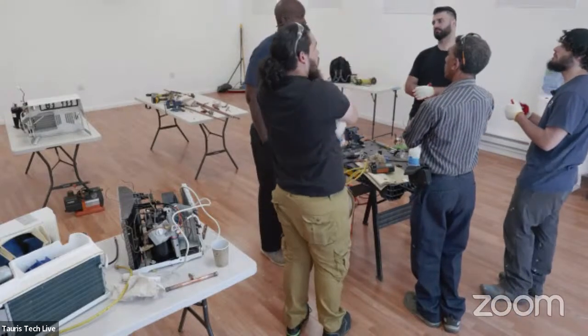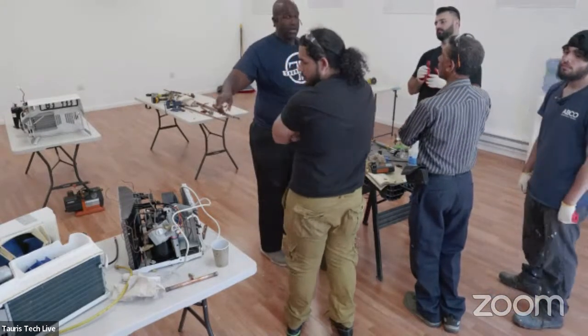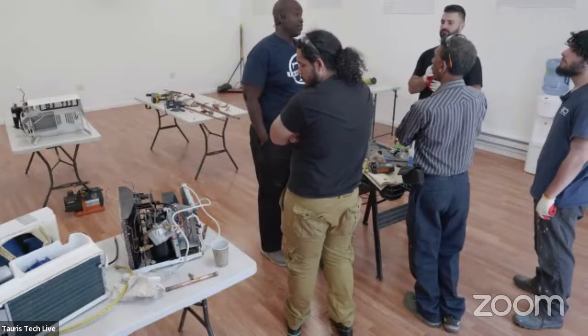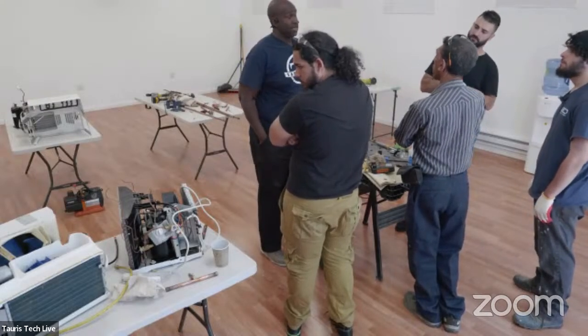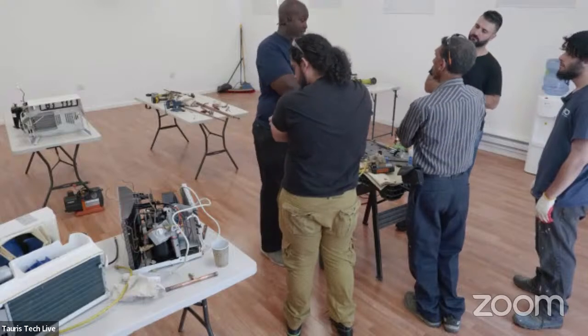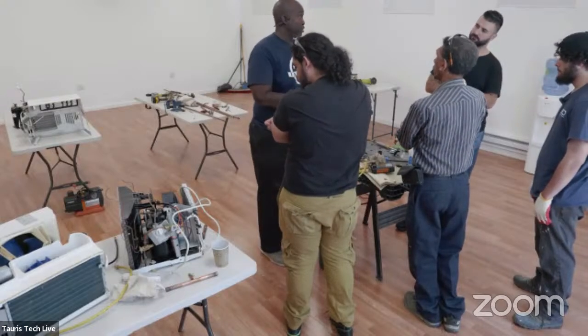Boiling moisture, the same way we were doing earlier running a recovery machine, boiling refrigerant. So the recovery machine is boiling refrigerant, and the vacuum pump is boiling moisture, boiling water.